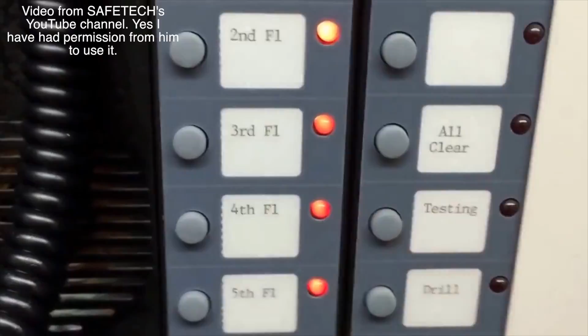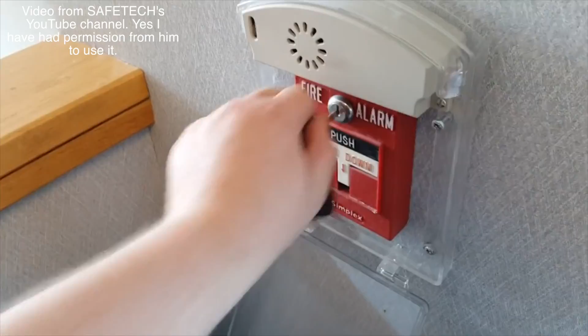Then I will proceed with going along and testing the initiating devices: pull stations, duct detectors, smoke detectors, heat detectors, pretty much what you all usually see in my videos of a regular standard fire alarm test. At the end, I will put the system back to normal and take it out of walk test. A lot of you may have seen me do this before. I'll set the system off in regular fire alarm mode, let it sound for a few seconds, and then do a reset. After that, that's how I verify with monitoring that a fire alarm signal has been received by them, and that if it were an actual event, they would react to it as their protocol states.